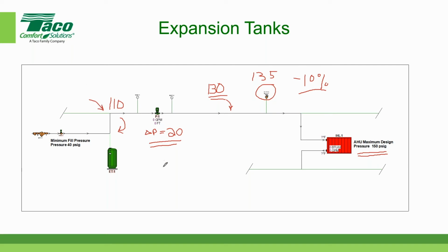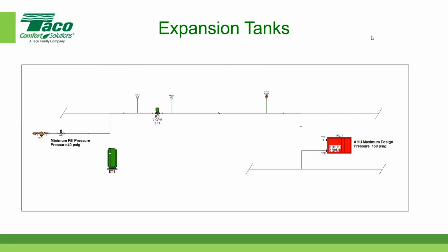So just repeating, let me go backwards now. If I had 110 at the connection of the expansion tank, which is the maximum pressure of the expansion tank, the pump added 20, that would be 130. If I wanted the safety relief valve to be 5 pounds above that, I'd set it at 135, and that's 10% less than the maximum working pressure of my system. So I can erase all my handwriting right now, and I can just put in all of the values that we just talked about. So now I've determined not only my minimum pressure or fill pressure, but I've also determined my maximum pressure at the expansion tank.